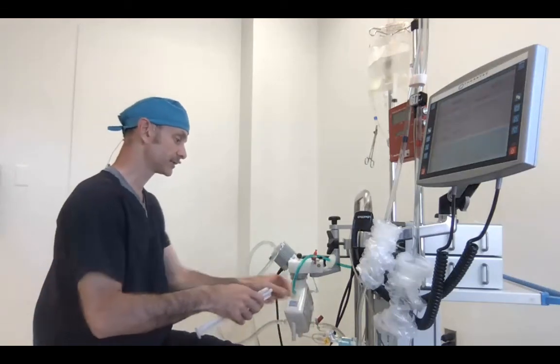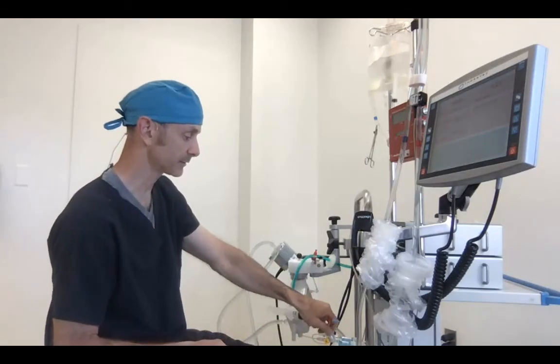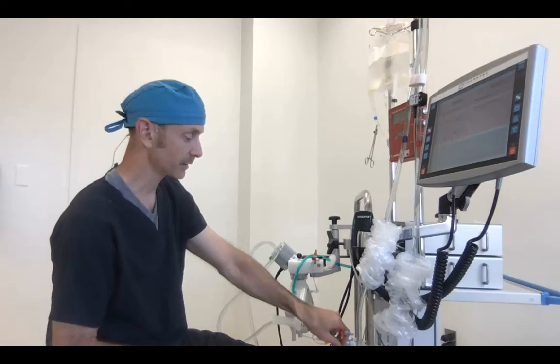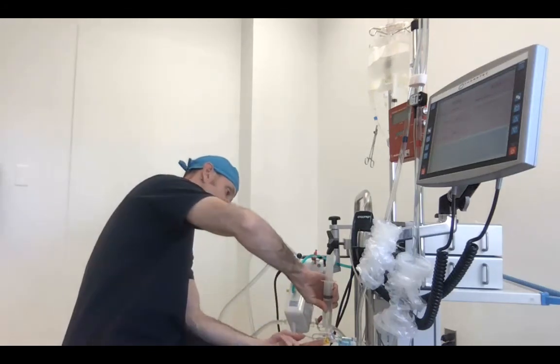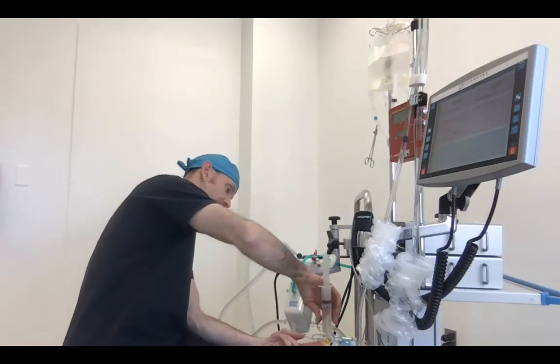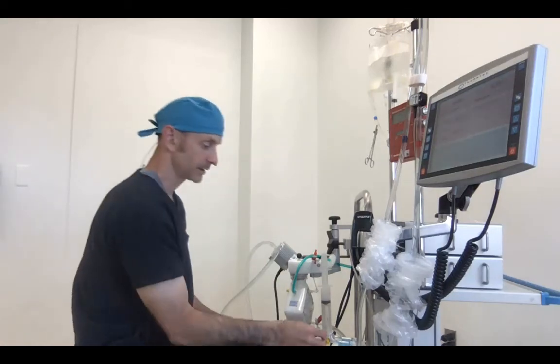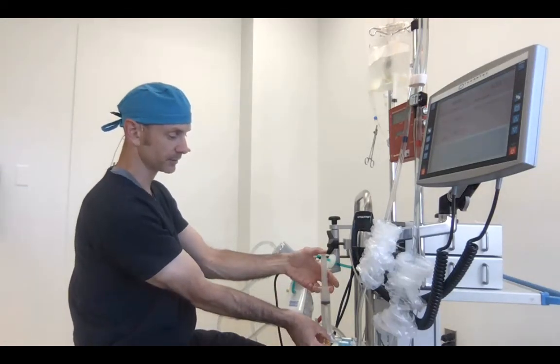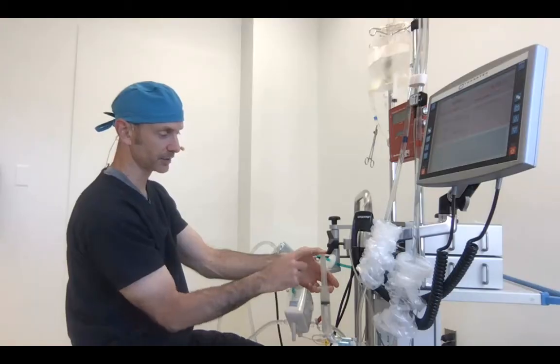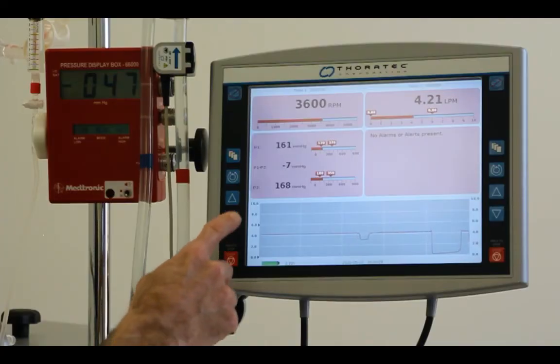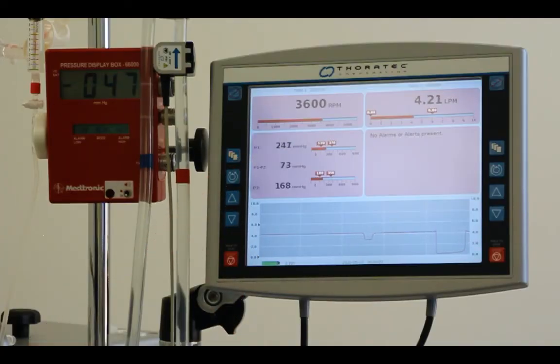And if you wanted to see how that would play out, then what I have to do is simply lie to this transducer and tell it that it's feeling a high pressure and let it believe it's coming from the oxygenator. So if I turn this stopcock off to my oxygenator and I start applying pressure here, you can watch P1 start to climb while P2 is holding steady. And this is what a failing oxygenator would look like.